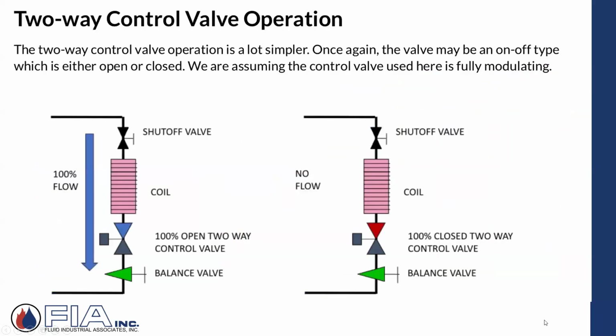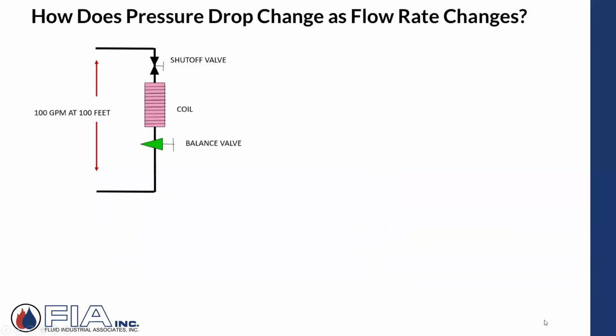So what would happen, again, just real quickly, if I'm dealing with two-way valves? They can be very simple. It could be on-off, or, and a lot of times most likely, modulating, where it would just fluctuate depending upon feedback from the indoor air temperature or space temperature in the area that it's controlling. But again, 100% flow, blue, 100% no flow or shut off, I should say, 100% closed, the red, or somewhere in between. One of the interesting things to think about is, how does pressure drop change as flow rate changes?